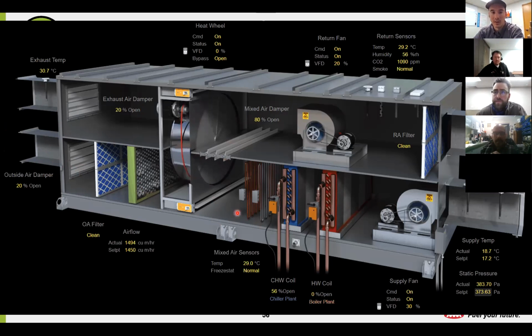This is a lot to look at here, but I'm sure a lot of you actually have exactly this kind of display for some of your units at your buildings. And one thing I didn't touch on is for this heat recovery wheel here, in cooling, you wouldn't necessarily be running it to recover heat from the space because we're trying to get rid of it. So in that case, you have bypass dampers where that shuts off and the air is just bypassing the heat recovery wheel.